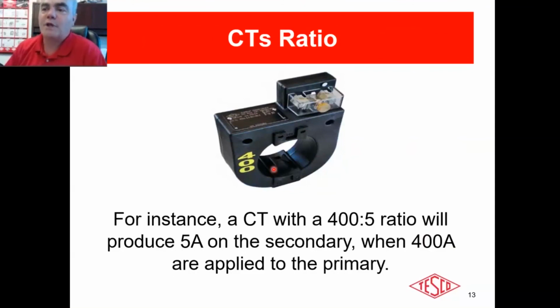This 400 to 5 transformer is a donut type, so the wire passes directly through. In a perfect world, you pass that wire directly through the center of that circle to give you the maximum accuracy. But the fact is, if you measure the accuracy with the wire up here, down here, up here, or in the middle, it is not appreciable. It's only with the best shop equipment could you even really measure it. It could be measured, but it's very infinitesimal.